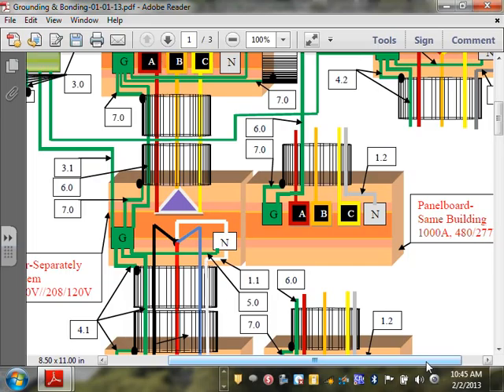Number 1, you have to provide number 6. You see that number 6? Number 6 is called the equipment grounding conductor, not grounding conductor, equipment grounding conductor. So you have to pull a 5 conductor cable or 5 conductors in a conduit between the 2 equipment. What are the 5? The 3 phases, the neutral, and an equipment grounding conductor. Now we all know that rigid metal conduit and EMT and a bunch of metallic conduits can qualify as an equipment grounding conductor, right? So that conductor number 6 could be your rigid metal conduit for all practical reasons. Does that make sense?